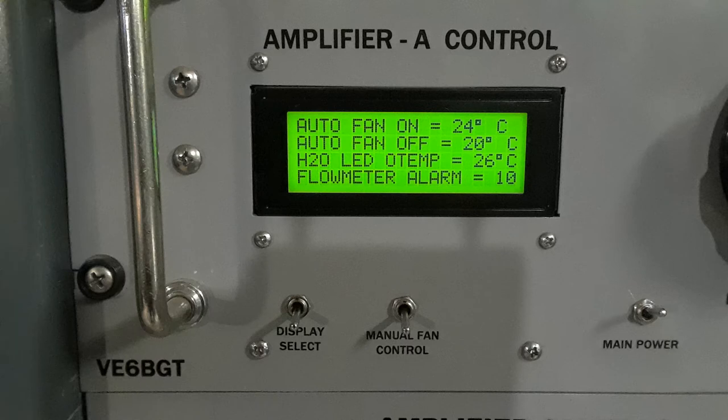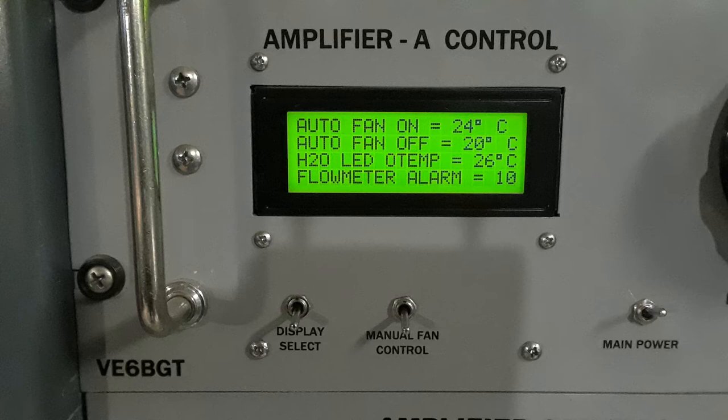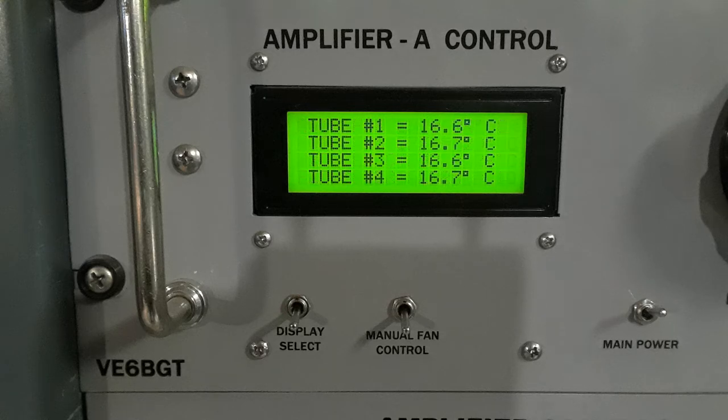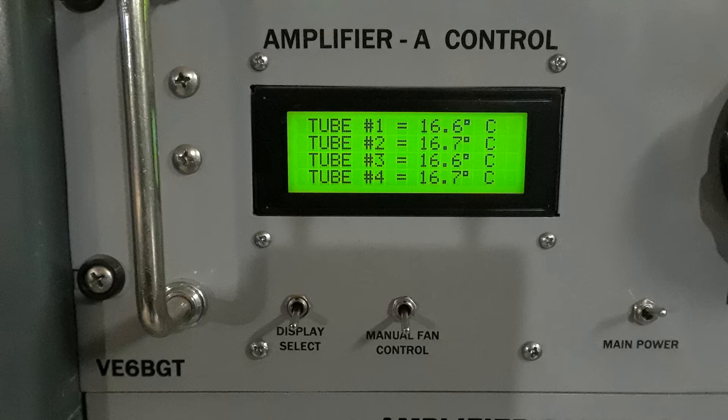The second part of the display is the set points, which are all adjustable from the front screen. The auto fan on is for the fans on the cooling tank. The auto fan off, of course, tells when it's shut down. The H2O LED over temp is for the over temperature LED. And the last one is the flow meter alarm, which is set for 10 pulses per second. If the flow rate drops below 10, it shuts everything down and shuts the transmitter off. The third part of the display is pretty self-explanatory. It's giving you the temperature of each individual tube circuit on the water lines.